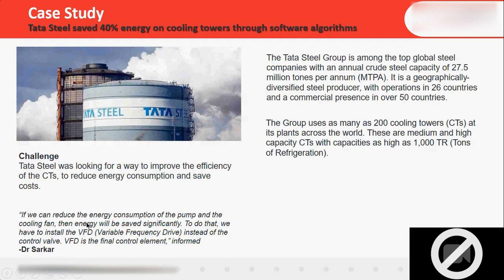Dr. Sarkar, who was dealing with this project, said that if they could reduce the energy consumption of the pump and the cooling fan, energy would be saved significantly. To do that, they had to install a variable frequency drive to control the cooling tower.